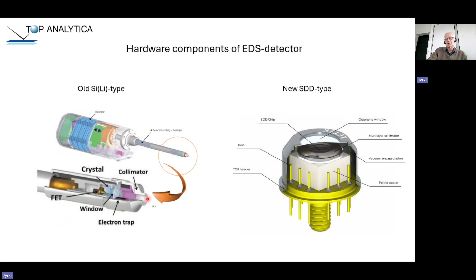If we look at the new SDD, silicon drift detector, it is quite different. Of course, we have a window in front of the detector. The SDD chip is situated here, and under that there is a Peltier cooling system which is keeping this detector cold. The temperature we have here is probably something like -20 up to -50. Instead, what we had here was liquid nitrogen cooling. So you see that the size of the detector part is much smaller than the previous one.